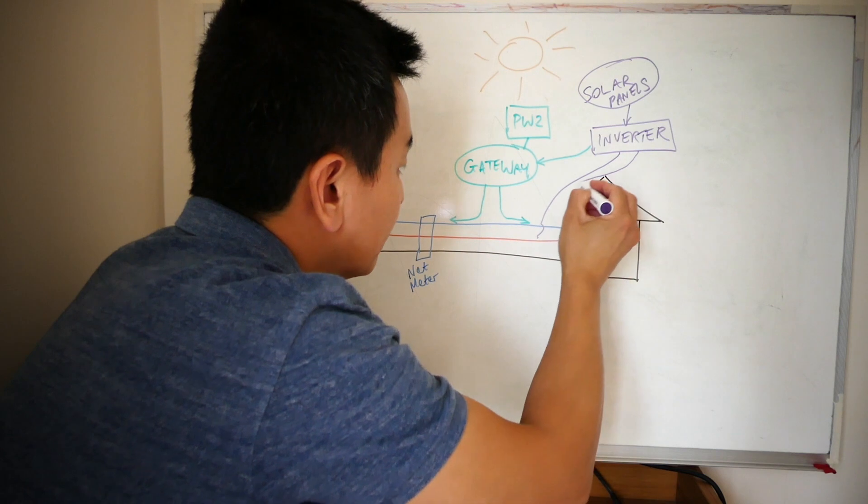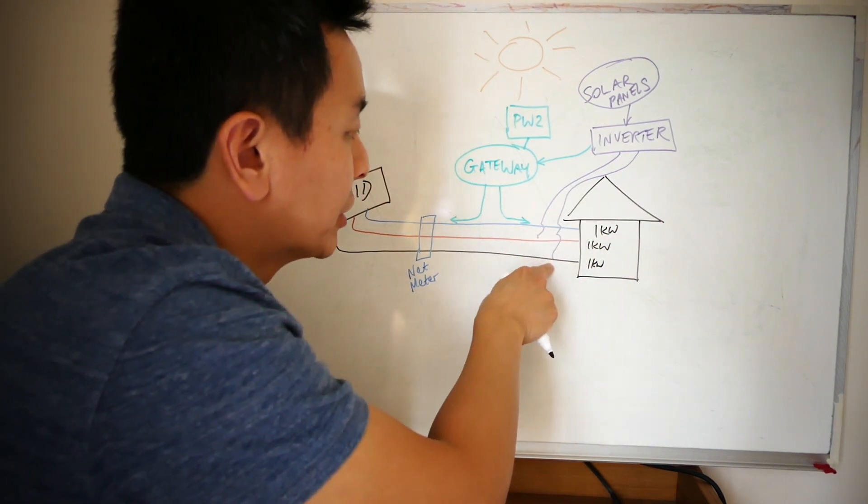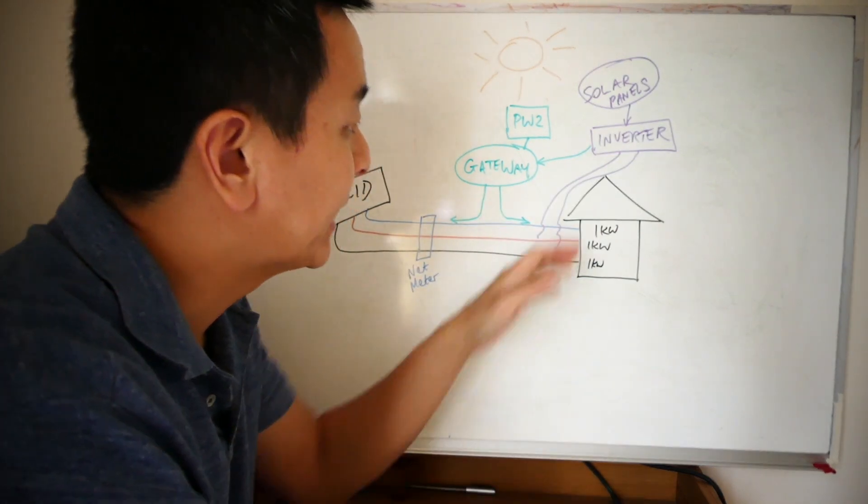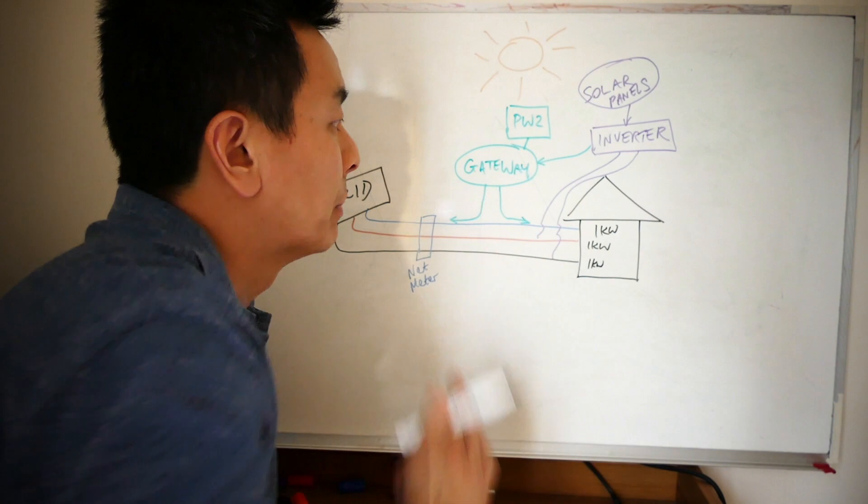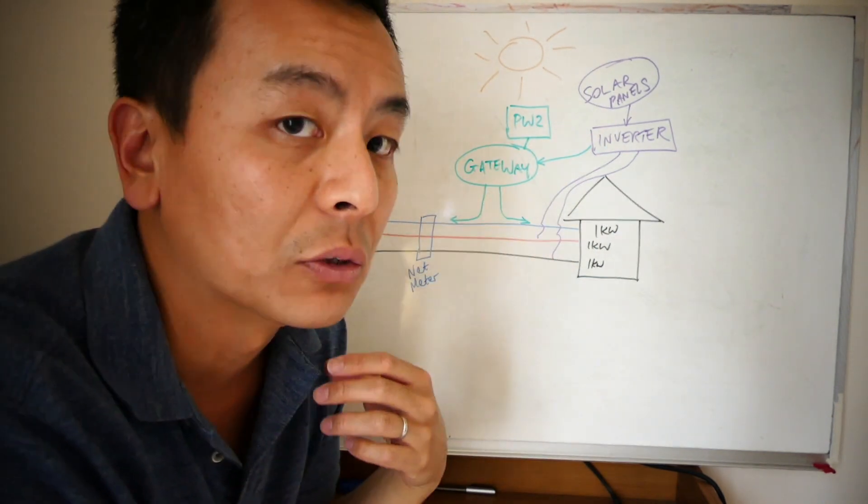Same with this one here: second phase going to this one, third phase going to that one, and the first phase goes to the gateway. So in reality, you're only going to get one third of the load from the solar panels charging your Powerwall 2. Not ideal, unless you've got a massive solar array, of course.